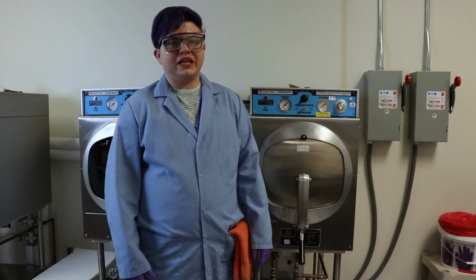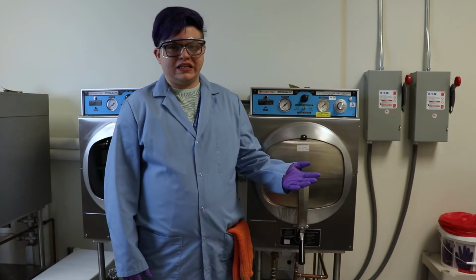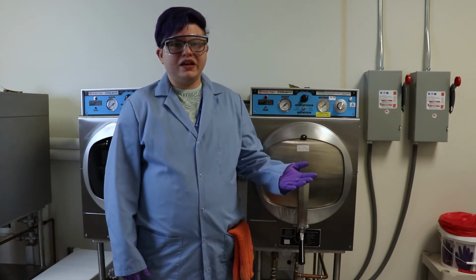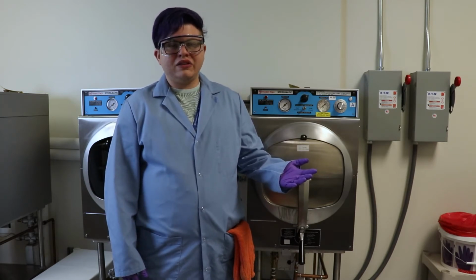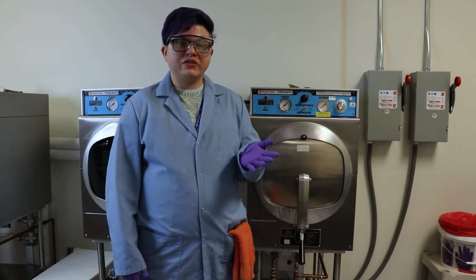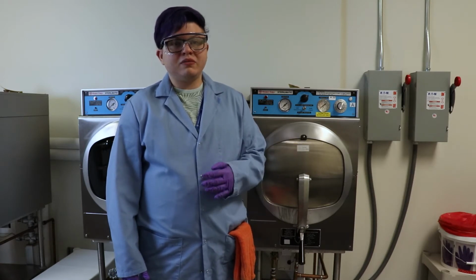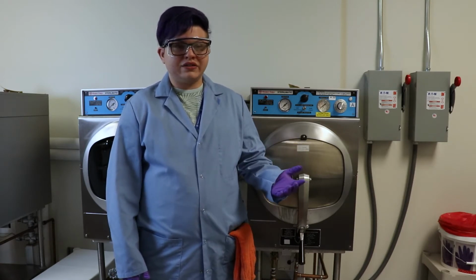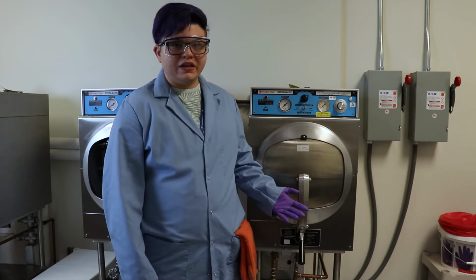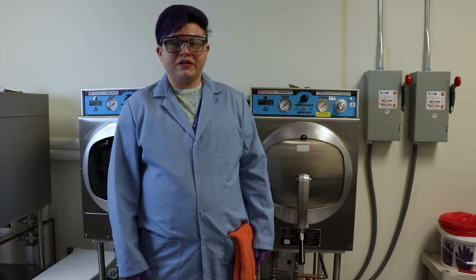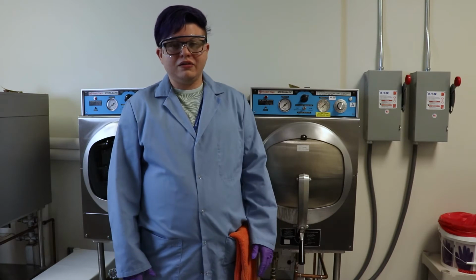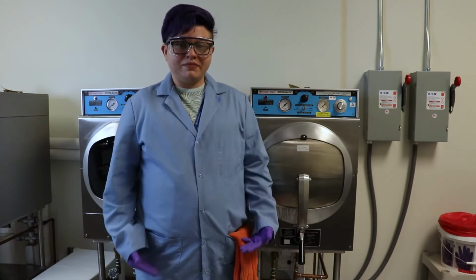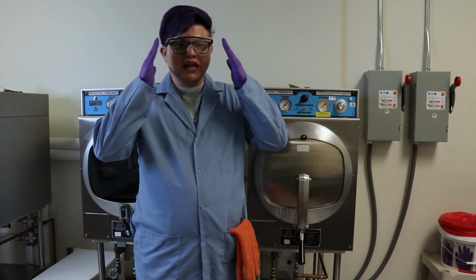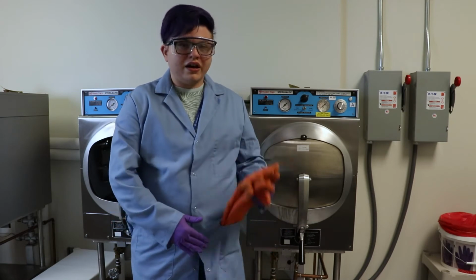When working the autoclave, there are many parts of safety that need to be taken into account. When decontaminating, you'll be dealing with both chemical hazards and biohazards, as well as the actual thermal hazard of the autoclave itself. So when working with the autoclave, you need to make sure you're wearing proper PPE, which includes gloves, a lab coat, safety glasses, and when the autoclave is hot, autoclave gloves.